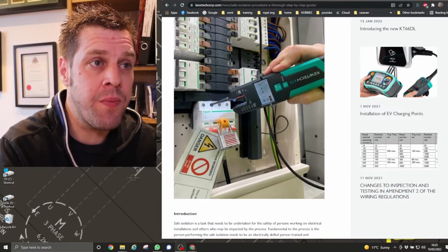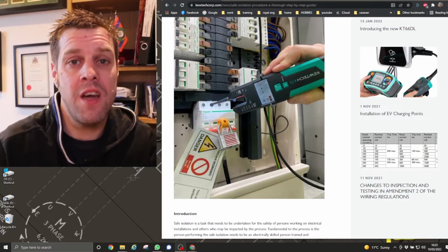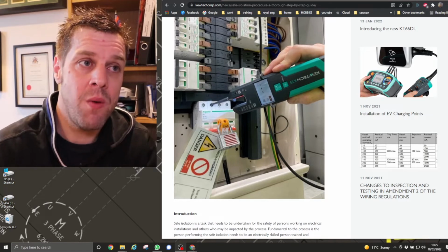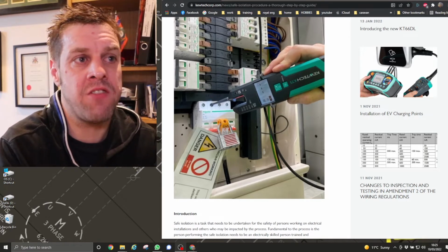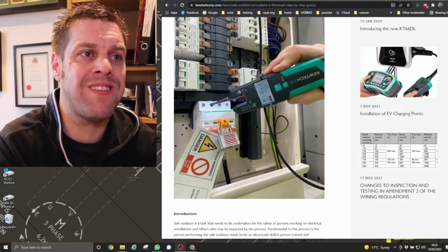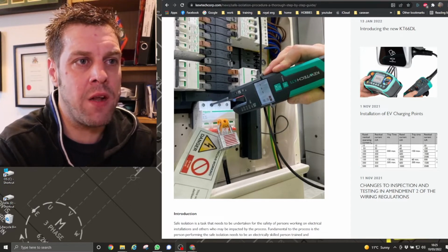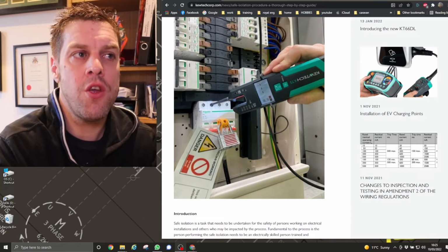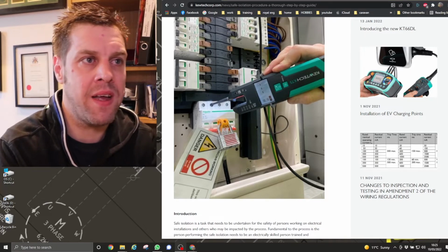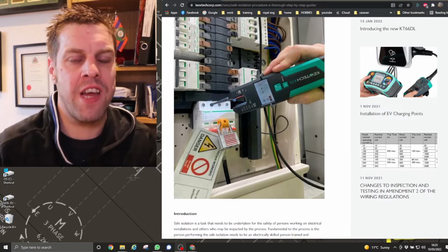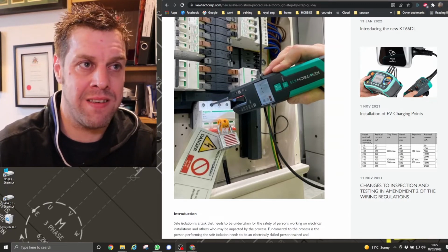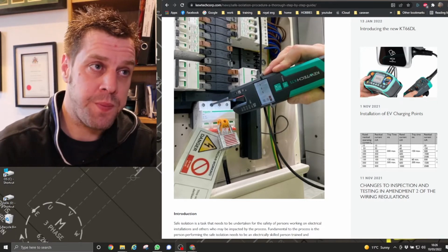In my opinion, this board in the UK will be fed as a radial, which means somewhere there is an isolator or a protective device on the other end of this cable. If you want to work safely in this enclosure, including this bottom bit, because there's a hole there, you need to go what I call one back. You need to go wherever this cable comes from and isolate it so the entire enclosure is isolated. This is bad form for me.